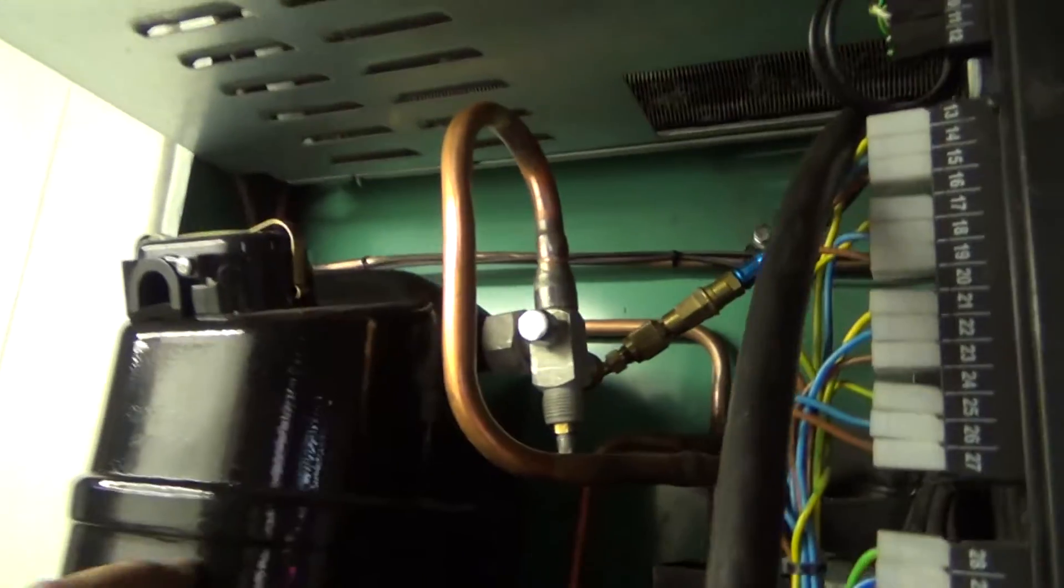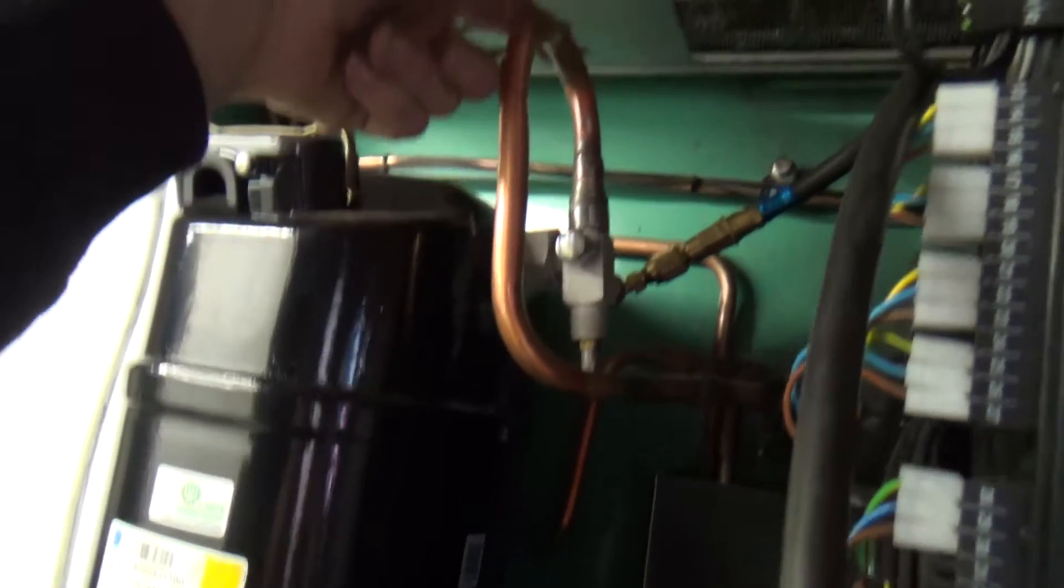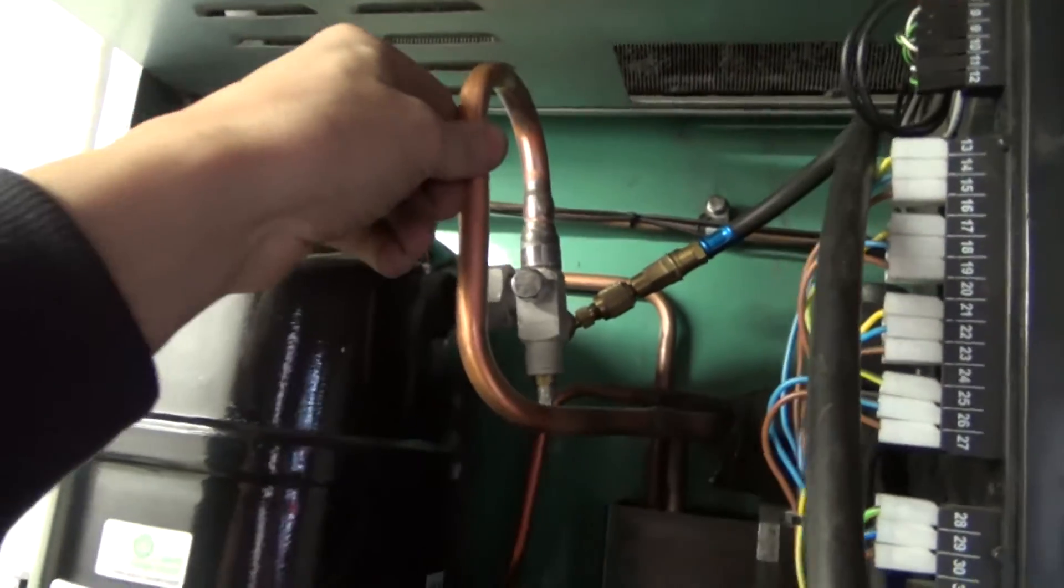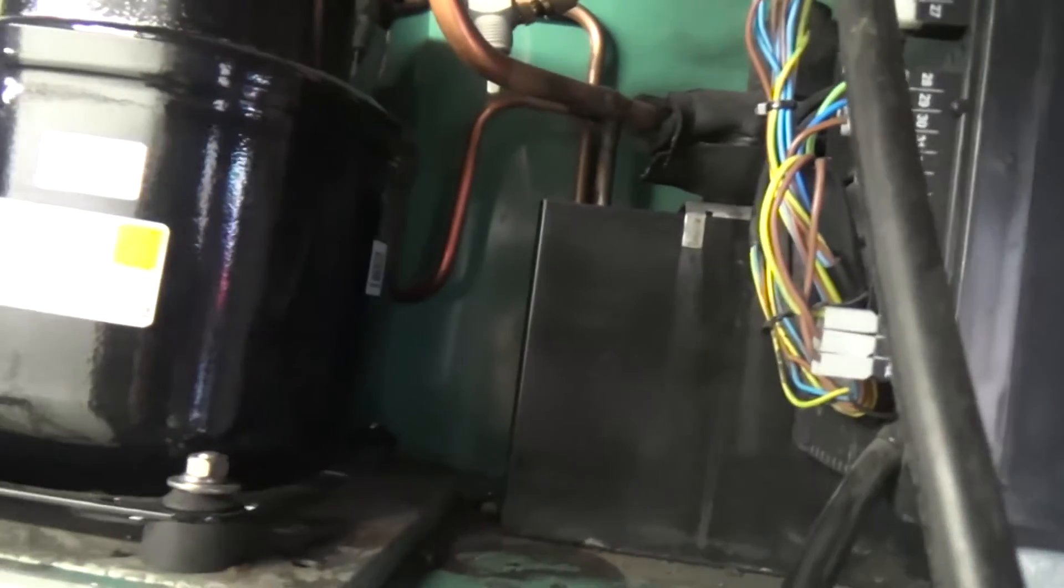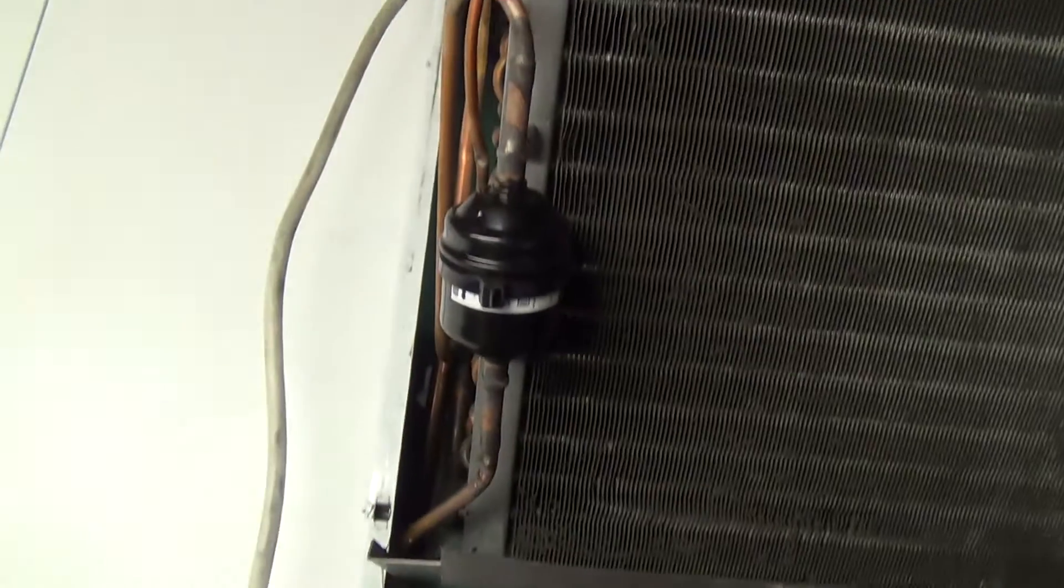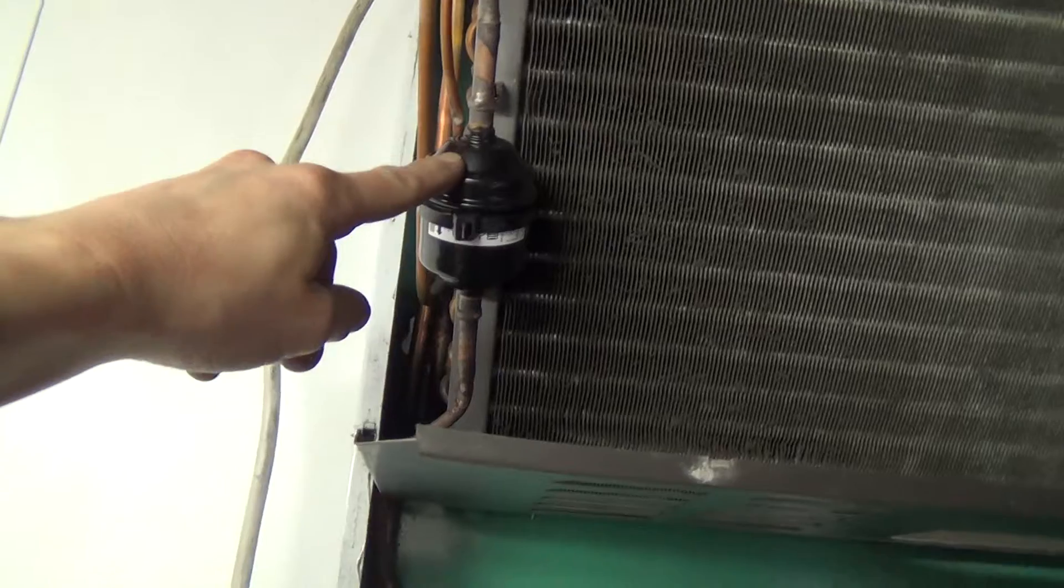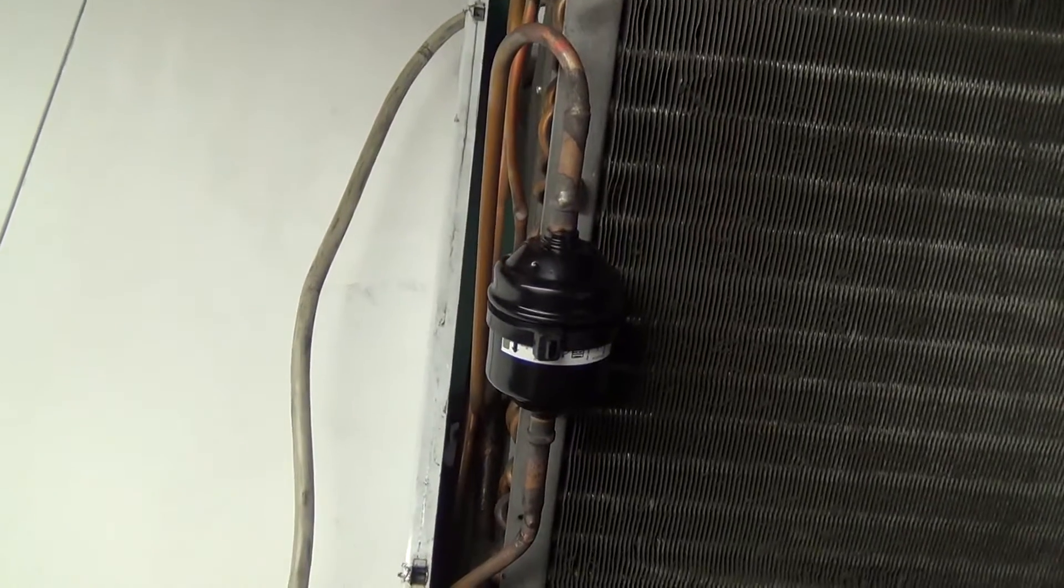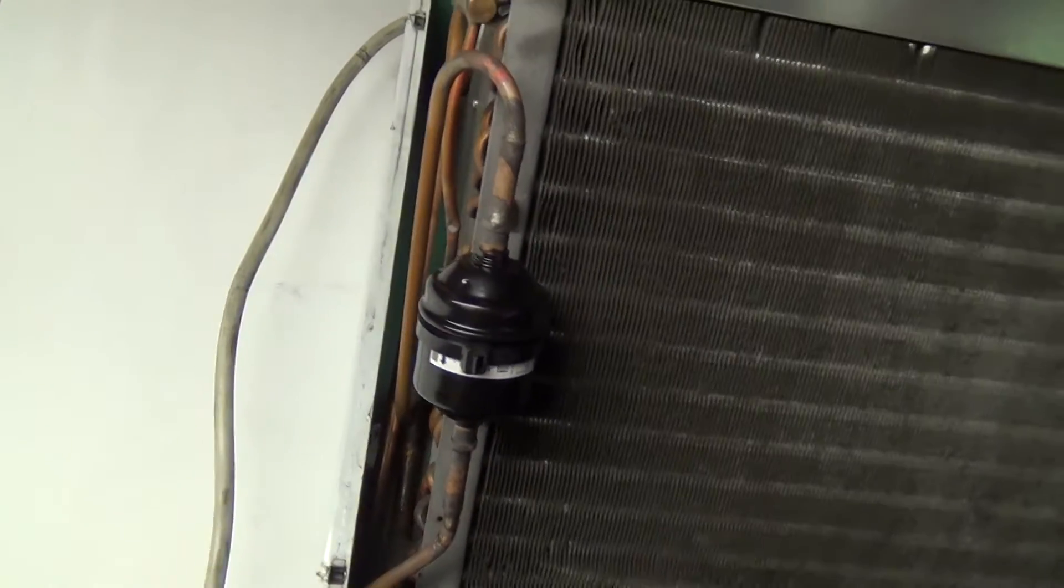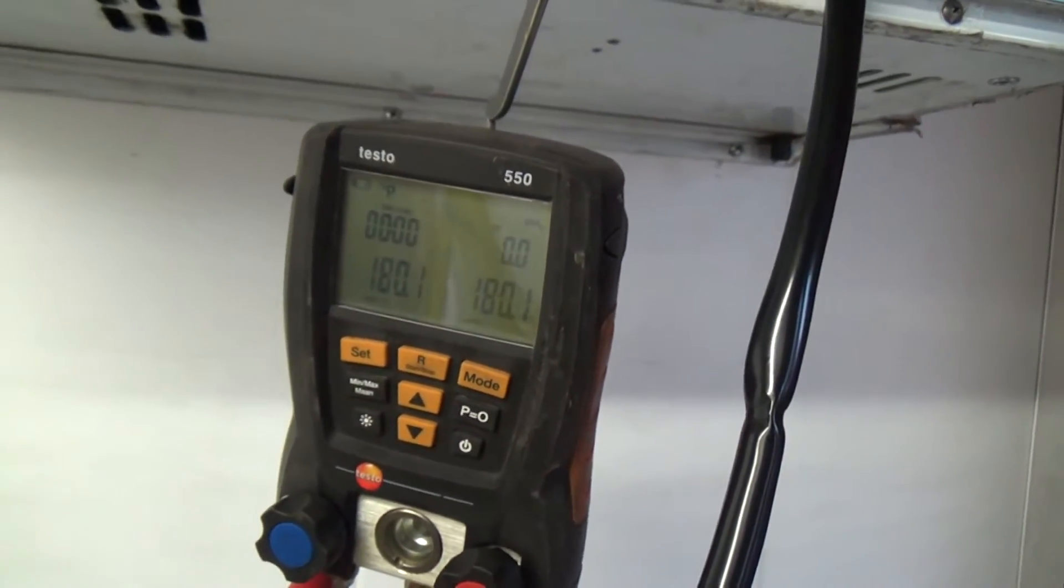Right, we've got the suction line brazed in. We've brought the pipe along up and linked it over the top into there. Hopefully that gives us enough room to put the electrics in here. Put a new dryer in there. It had one of them copper spun ones with the beads in, so we've gone back with one of these solid core Danfoss ones. We've just got it under some nitrogen in there now. Kind of a sandwich. And see how that does.